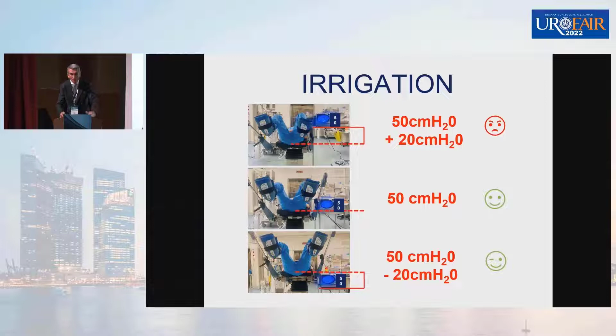If you place the pump exactly at the same level as your patient, then the pressure is exactly the one that you set on the pump. And if you place the pump below the patient, you will have to reduce the pressure. So it's not 50, it will be 30. And that's what we recommend: same level or below. But be careful if you place the pump above. This is a very simple trick.